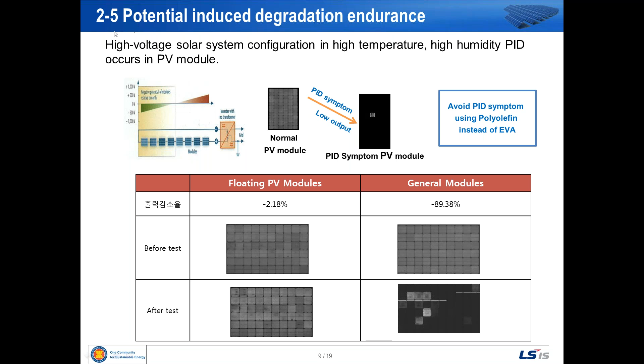The first evaluation of module degradation is for the floating PV modules. We collected 100 installed modules and measured them in the STC state once every 2 years. So we have conducted 2 measurement times. As a result, the average output reduction rate per year was 0.07%, and the standard deviation was 0.59% for 4 years. The actual output reduction is not the average output decrease, but the output reduction that takes into account the module standard deviation.